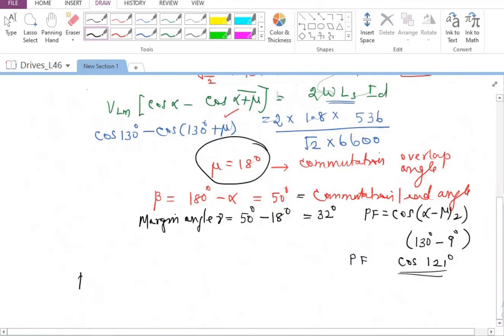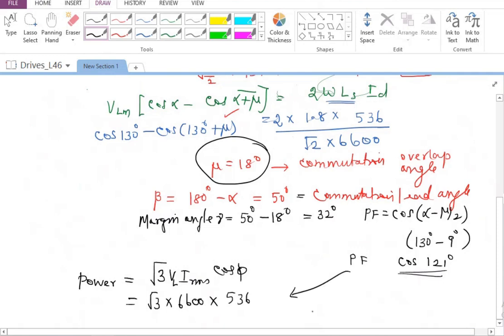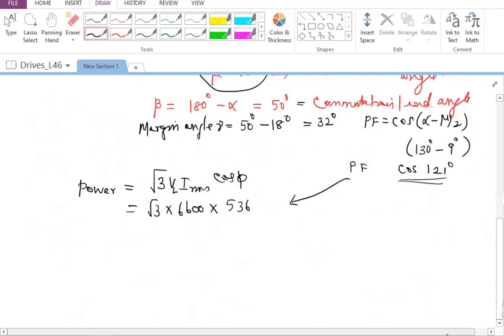Now the next thing is power. Power is going to be 3V IRMS cos phi, or root 3 VL IRMS cos phi. So I should calculate root 3 multiplied by 6600, multiplied by IRMS which is 536, and whatever is the power factor. Using that, we calculate the total power, and once you calculate the developed power, you divide it by omega, which is 104.76 radians per second.